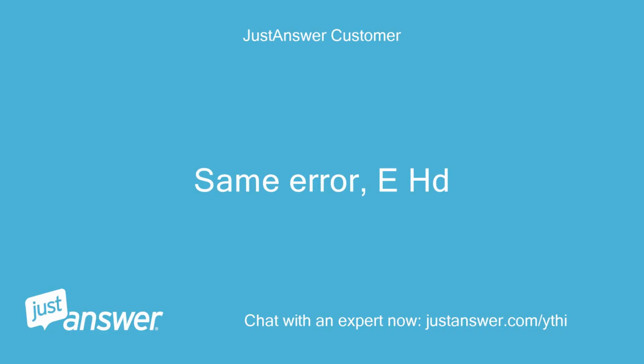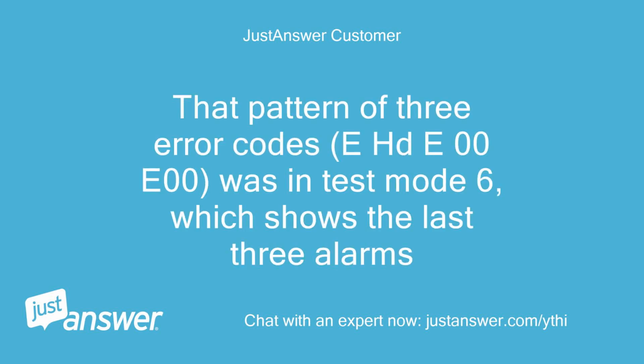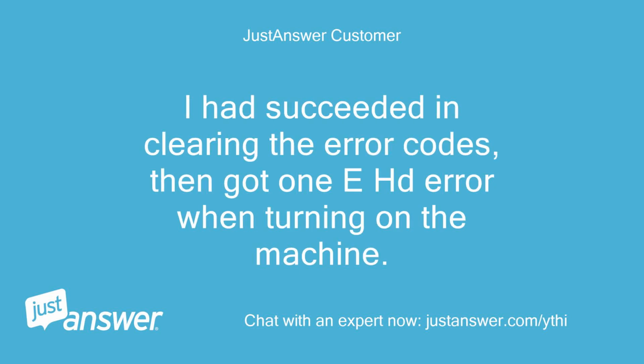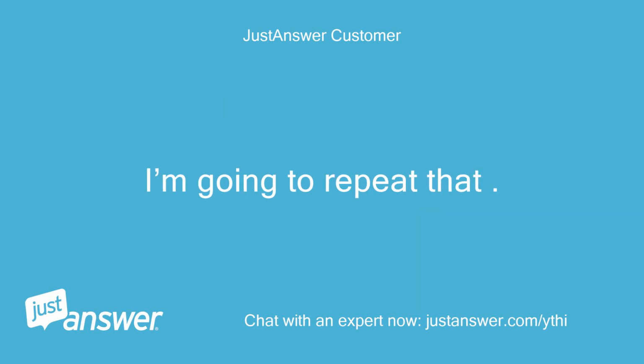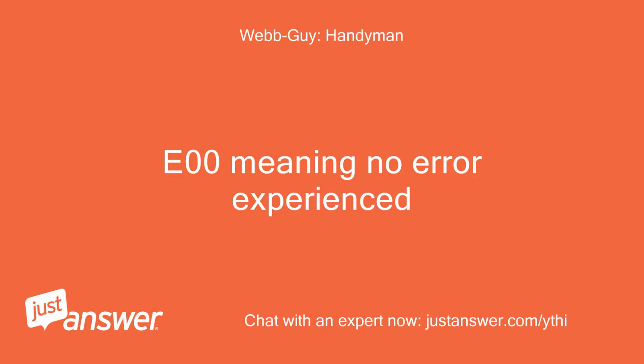Same error, EHD. That pattern of 3 error codes, EHD E00 E00, was in test mode 6, which shows the last 3 alarms. I had succeeded in clearing the error codes, then got 1 EHD error when turning on the machine. I'm going to repeat that. E00 meaning no error experienced.